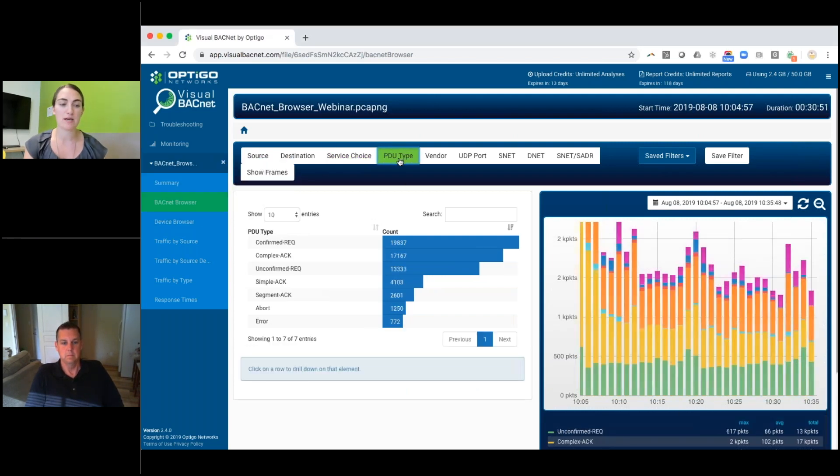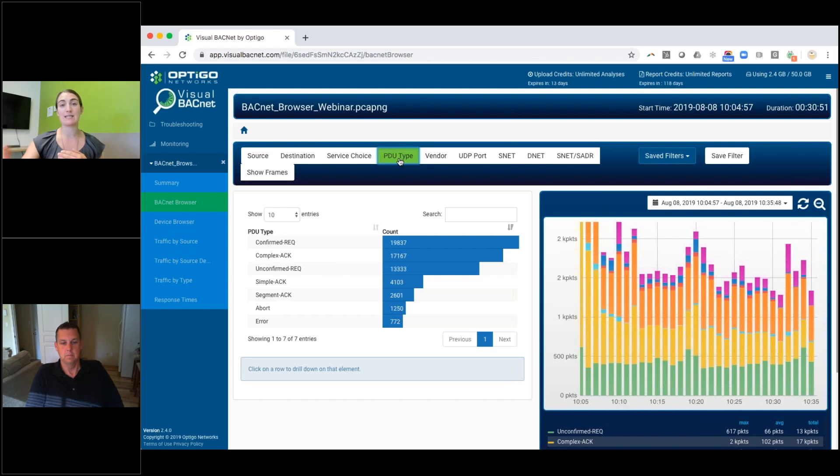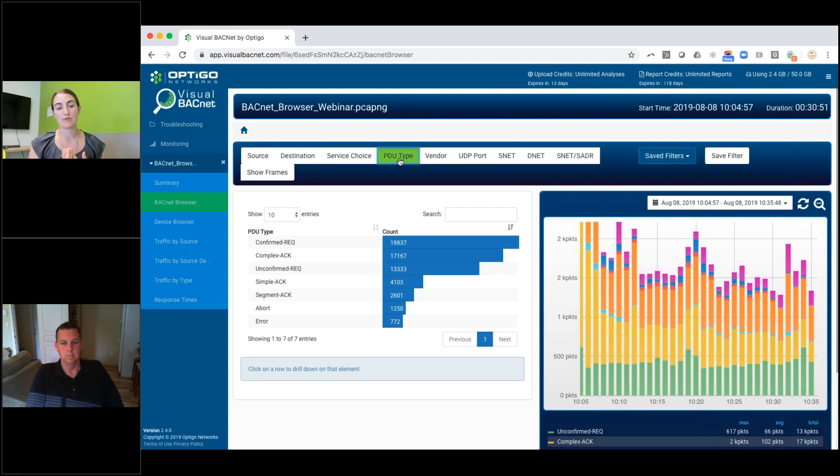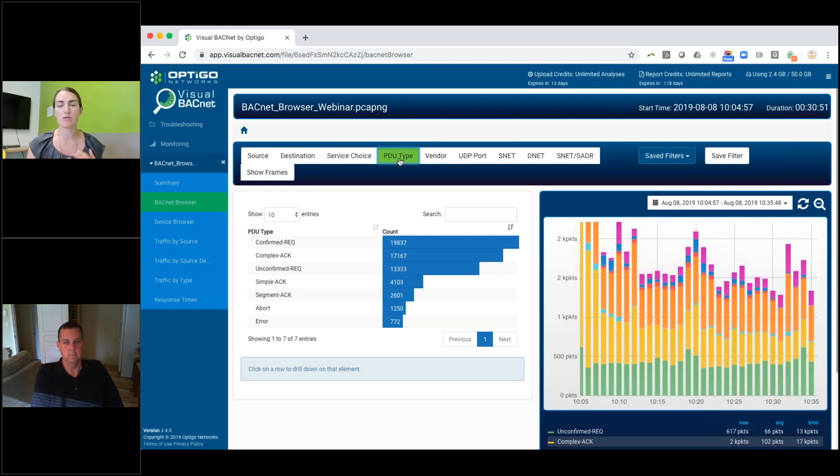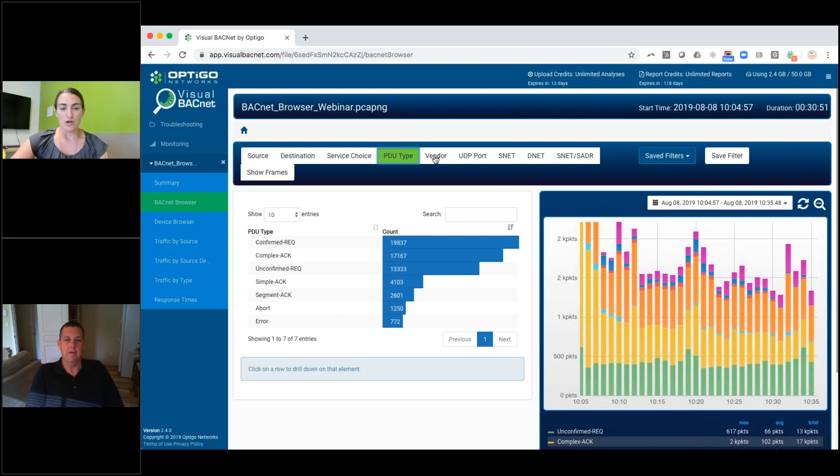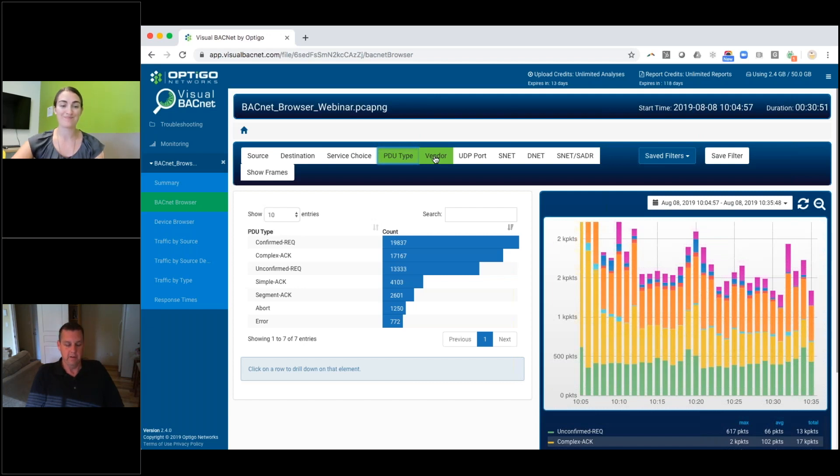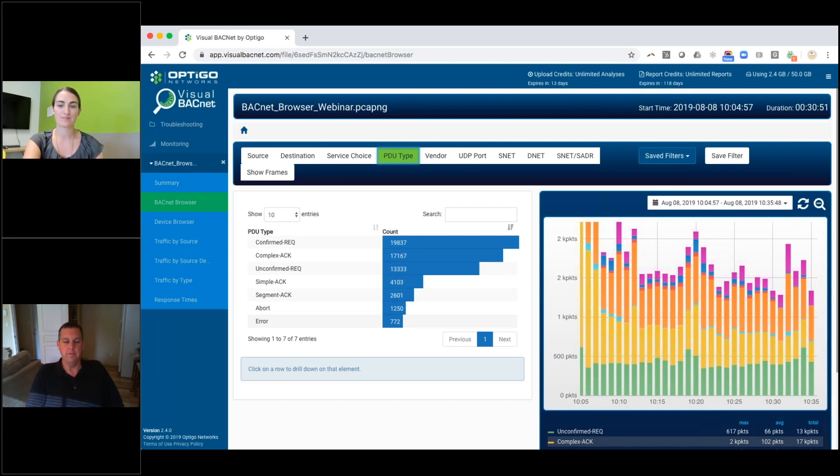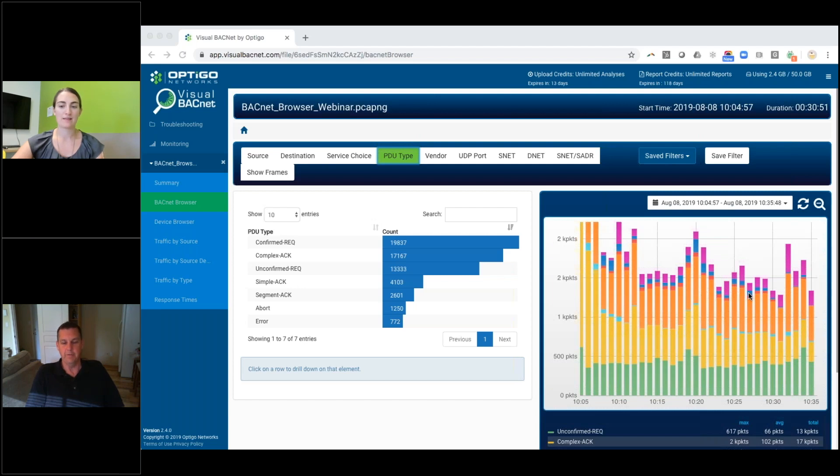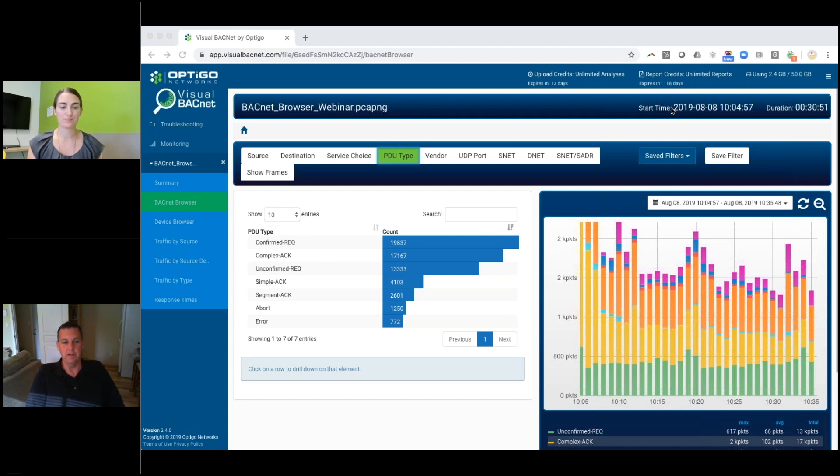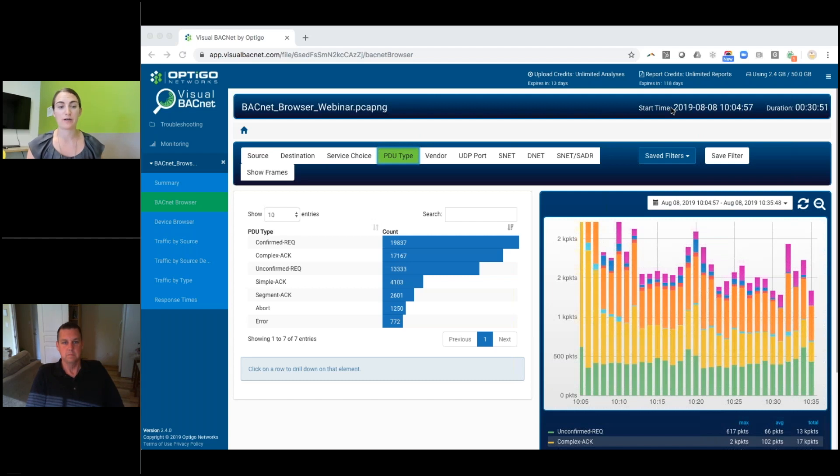PDU type, it's looking at the type of packet. So is it a confirmed request? So it's a request that needs a response, a complex acknowledgement, an unconfirmed request. So it's a request that shouldn't have a response, simple acknowledgement, segmented acknowledgement. It's a few different options here. I don't look at this one a ton, but it can be useful when we get into drilling down. Just I want to add a point here, Monica, just at the very bottom there, you see a couple extra ones, the abort and the error packets. These are very common when you're interacting with third party devices. Maybe your piece of equipment is sending some information and it's in error. Maybe the third party device doesn't accept that type of packet, where in that case, you'd have to refer to the BACnet statements and that sort of thing to determine. But that's a pretty good way of very quickly determining what's going on. Yeah. And the error ones will also show up in our error response diagnostic check.